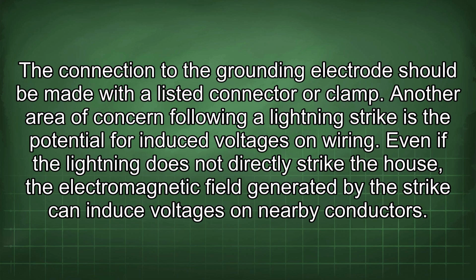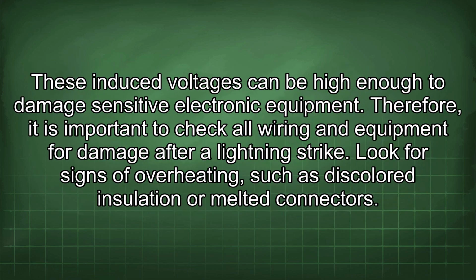Another area of concern following a lightning strike is the potential for induced voltages on wiring. Even if the lightning does not directly strike the house, the electromagnetic field generated by the strike can induce voltages on nearby conductors. These induced voltages can be high enough to damage sensitive electronic equipment. Therefore, it is important to check all wiring and equipment for damage after a lightning strike.